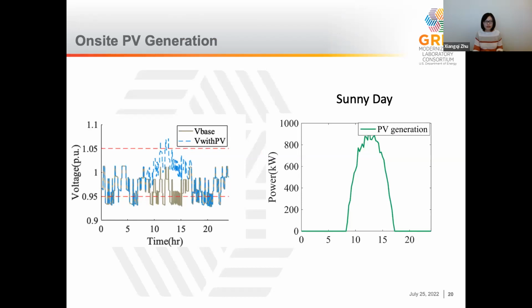We have developed some mitigation strategies which can potentially benefit the feeder for charging station hosting. Reactive power support is assumed to be a function of the charger to effectively boost the voltage when the charging load is lowering the system voltage. However, when the charging load is significantly high, reactive power can no longer effectively raise the voltage, and some on-site real power generation is needed to offset part of the charging load.